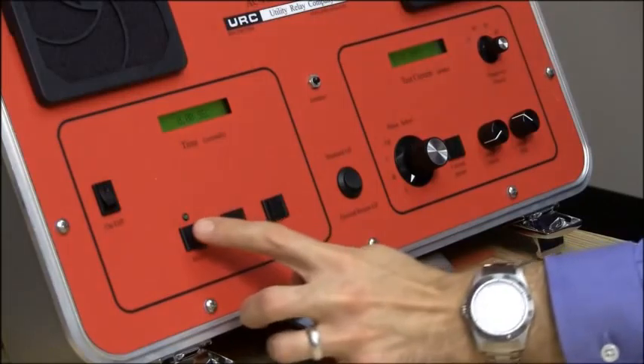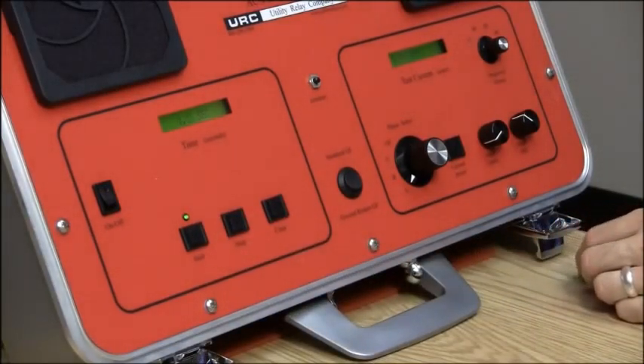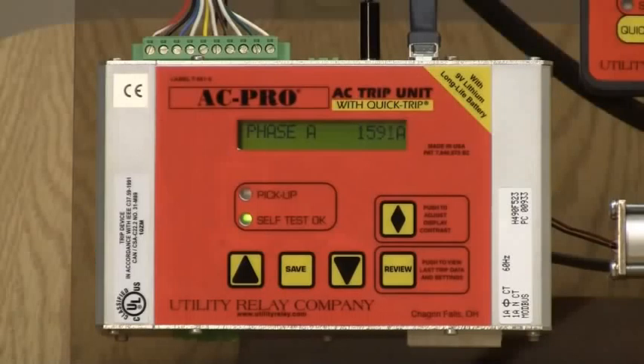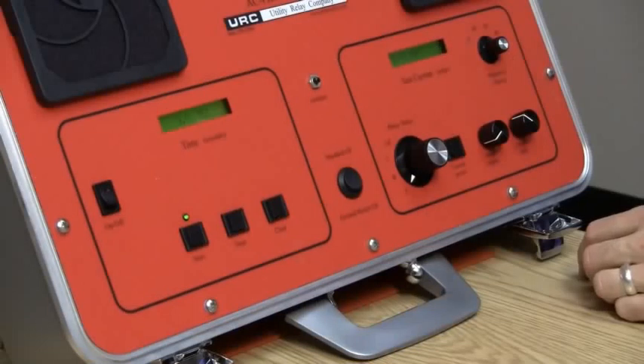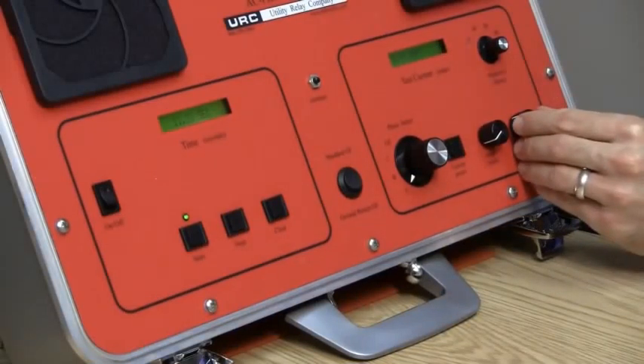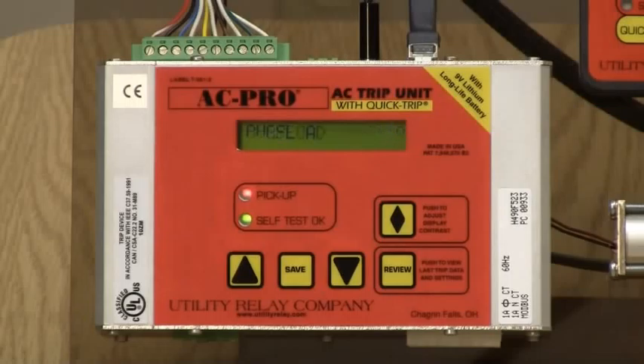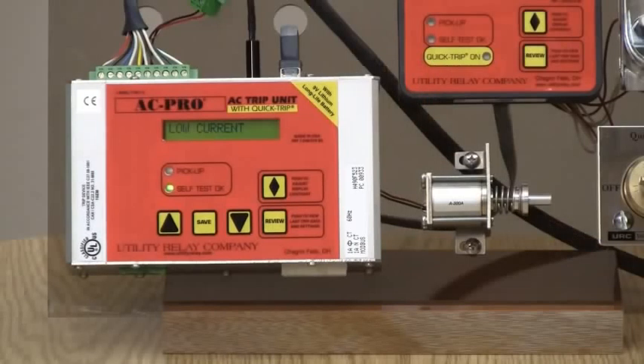I'll start the test set current at 0.98 amps on phase A, and we can see that the pickup LED is off and the display shows phase A current just less than 1600 amps. Now increasing the test set current to 1.02 amps, and we can see that the pickup LED is now on and the display shows just over 1600 amps. As you can see, the long-time pickup on phase A is well within our stated accuracy of plus or minus 10%. Now let's do a long-time trip using the secondary injection test set.